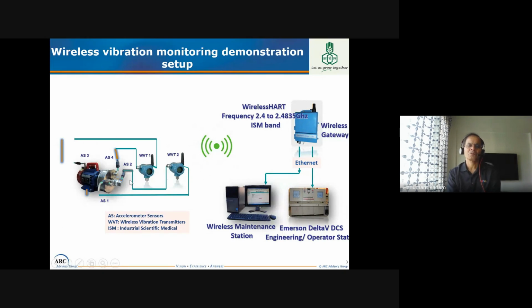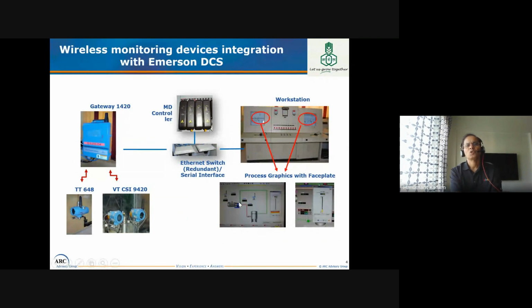These two transmitters with four measurement points. Each transmitter has two, so total four points of measurement at this motor side, here and here. At the pump side also you can see here and here. And these vibration signals are taken to the DCS in the wireless format, and then the gateway is either Ethernet or Modbus, or nowadays this gateway to system is also wireless to the Emerson DeltaV DCS here. And this is a separate station. If you have a PC dedicated for wireless configuration, then there also you can configure the devices on your PC here.